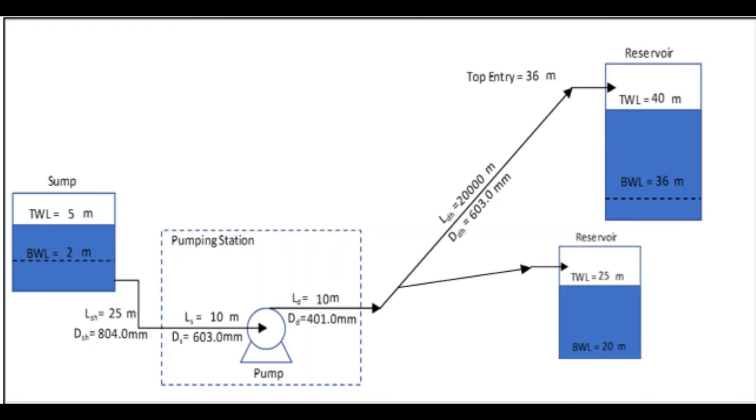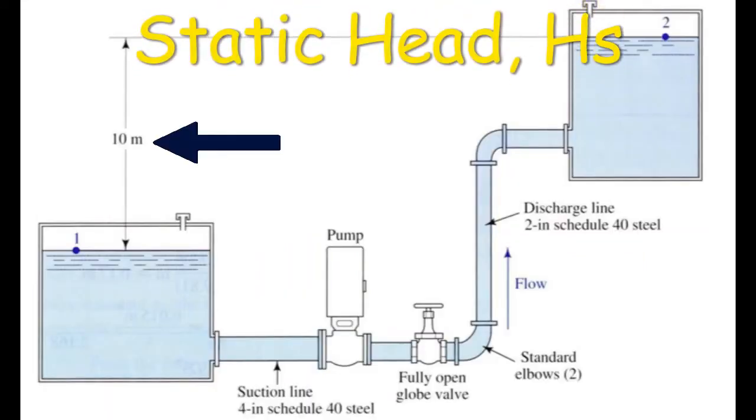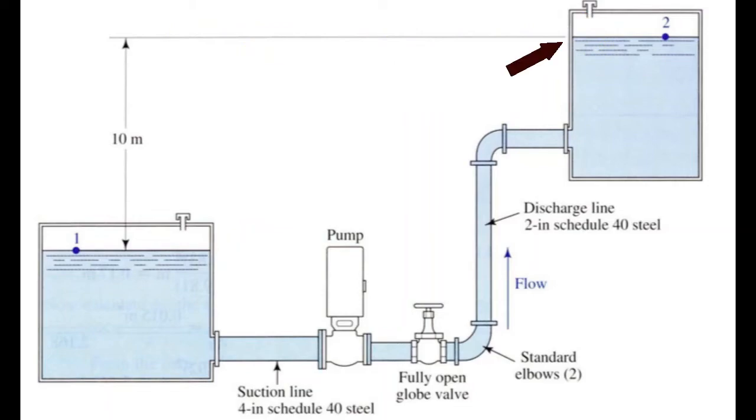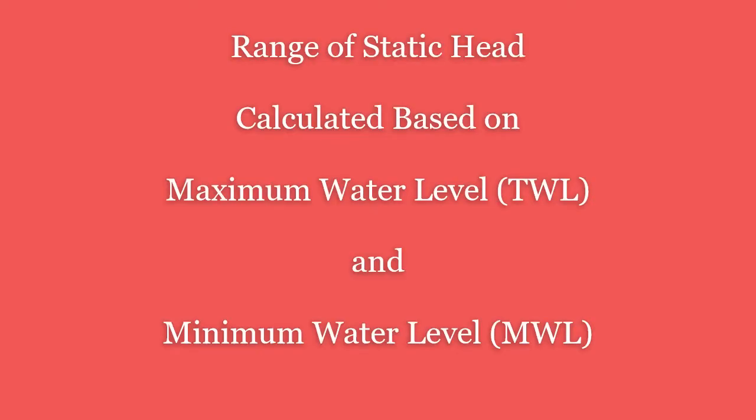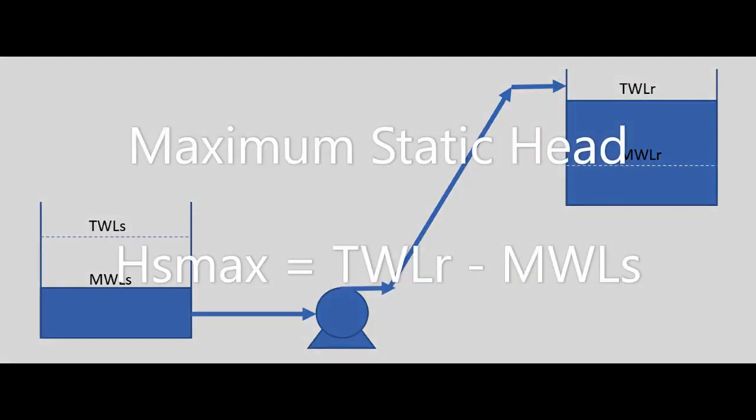Next, let us determine the static head, HS. The static head will be determined from the suction tank water level and the receiving end water tank level. HS equals receiving tank water level minus suction tank water level. In order to examine the range of head required, the static head shall be calculated based on the maximum and minimum water levels at both tanks. The maximum water level at the receiving water tank minus the minimum water level at suction tank will give you the maximum static head.